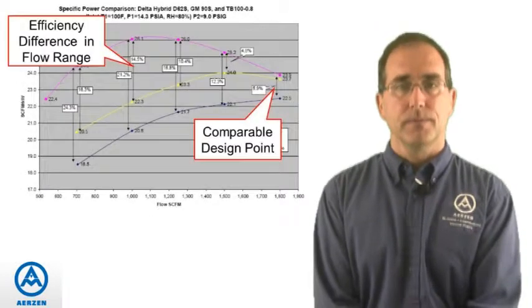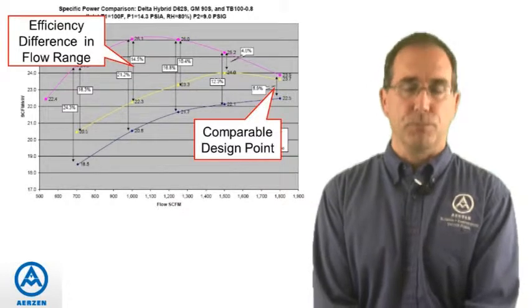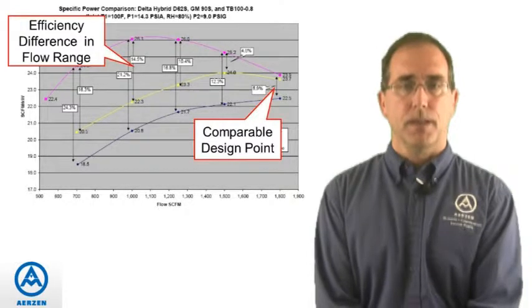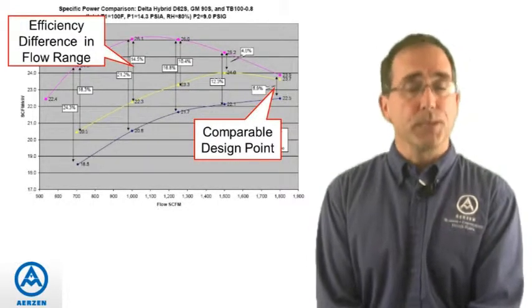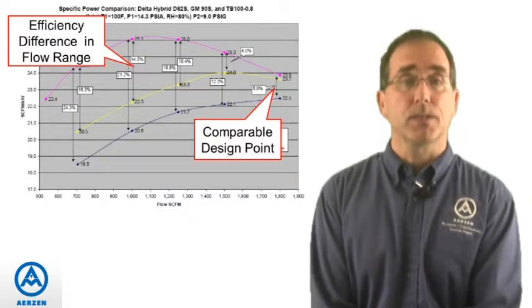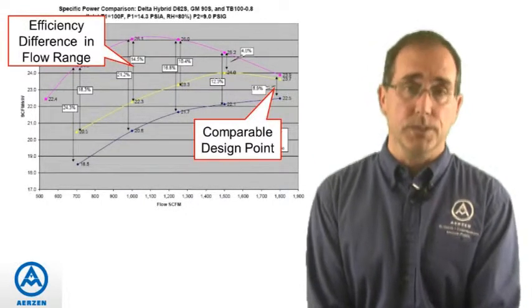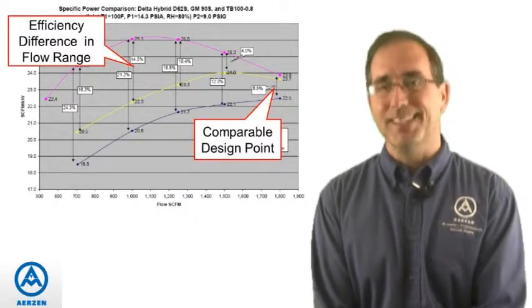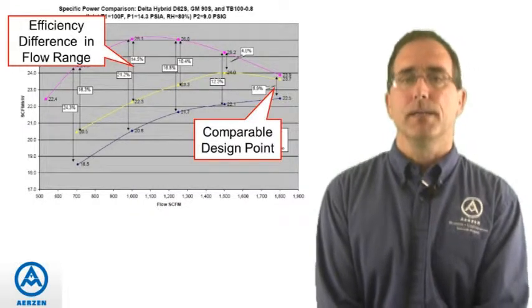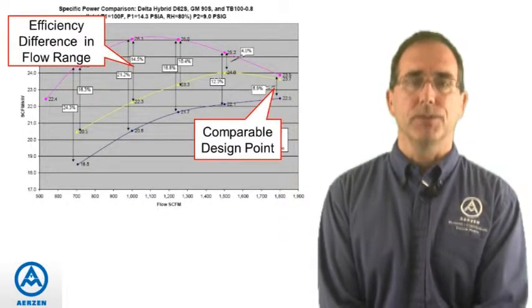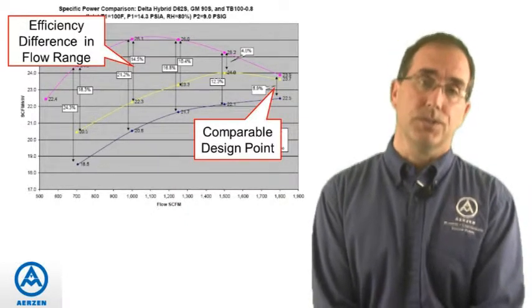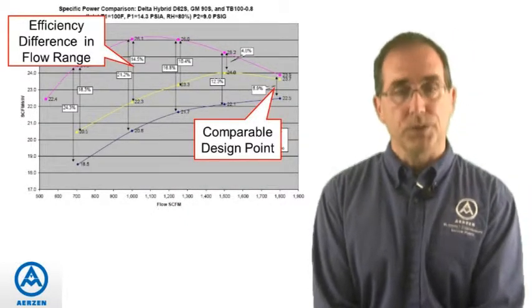The next curve is another set of comparisons between the three technologies. As you can see, at the design point the hybrid and the turbo are pretty close. So if all you were doing was a design point analysis, it might be a toss-up and then you'd start to look at cost considerations — installation, maintenance, footprint, that sort of thing. But if you went beyond just the design point and started to look into the turndown range, you would see that the hybrid is actually much more efficient in the lower ranges than either the turbo or the standard PD blower.